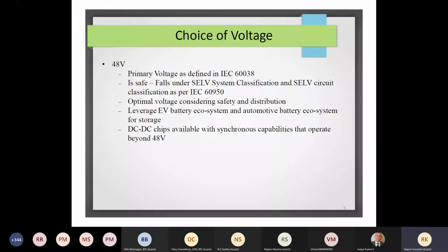There's always this conflicting requirement of having a higher voltage, because it will reduce current requirements and attendant I squared R losses during distribution, versus safety. If we go beyond 60 volts, we are looking at a scenario where the cost needed to put in the safety ecosystem would be prohibitive. So that's the reason why we chose 48 volts.